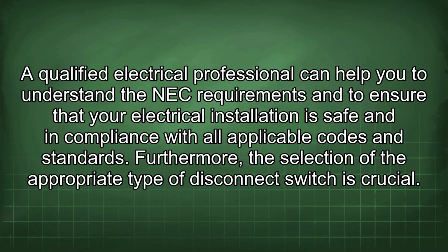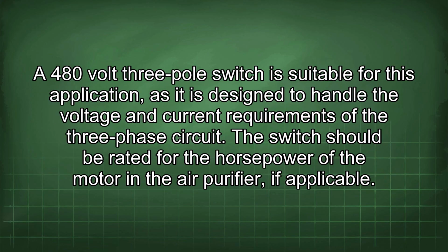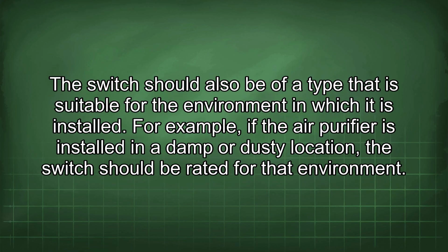Furthermore, the selection of the appropriate type of disconnect switch is crucial. A 480-volt 3-pole switch is suitable for this application, as it is designed to handle the voltage and current requirements of the three-phase circuit. The switch should be rated for the horsepower of the motor in the air purifier, if applicable. The switch should also be of a type that is suitable for the environment in which it is installed. For example, if the air purifier is installed in a damp or dusty location, the switch should be rated for that environment.